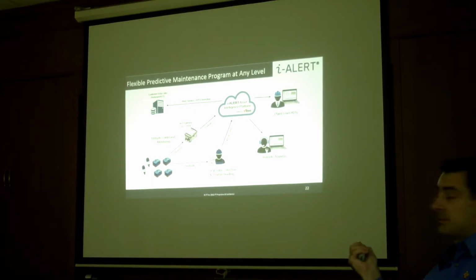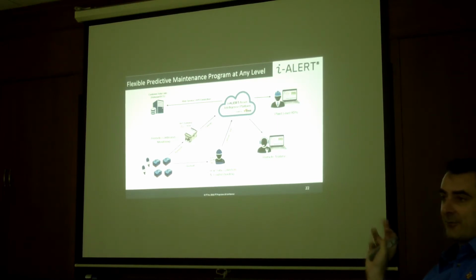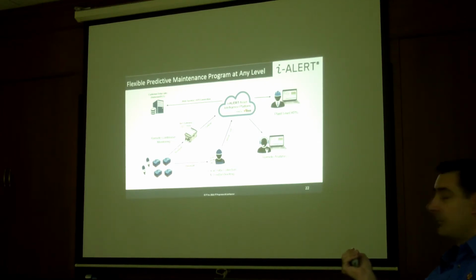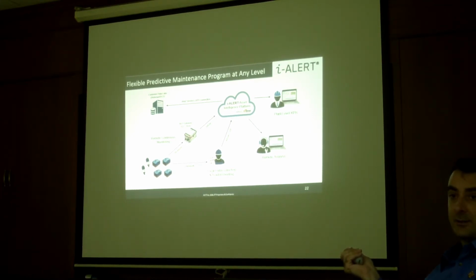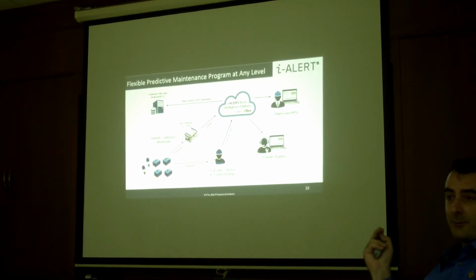This is perfect for vibration analysts, the way it's stored. It's set up for a vibration analyst, for anyone who's going to do troubleshooting and root cause analysis. With the gateway, eliminating this person, this is continuous monitoring. So we now make the system go from offline to online. As soon as one of these sensors goes into alarm, it sees it and sends it to the cloud. If it's set up correctly, it will send you an email notification straight away. So we can pick up alarms very fast now with the gateway.